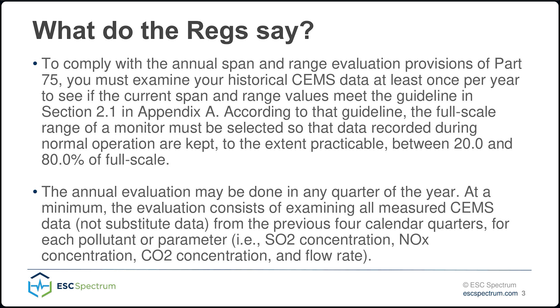This can be done in any quarter of the year. Since I'm a regulatory engineer, I have my own customers on my own schedule. I'll put in my data review to do span and range in January, looking at the past four calendar quarters. To comply, you must be within 20 to 80% of your full-scale range. This does not apply to the high end of NOx. I do that every year for my customers, and if something's off, we talk about it, make sure it's applicable, and make a change when necessary. So if you think your MER is too high, you should be doing this span and range evaluation — maybe find a new MPC to put you back in that 20 to 80 range, and then you'll have a new MER.